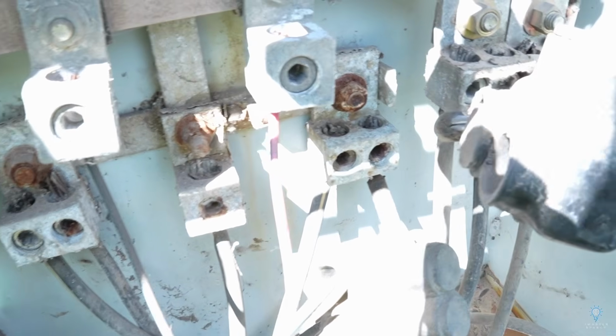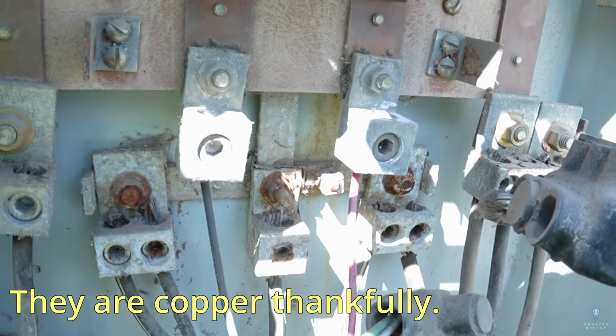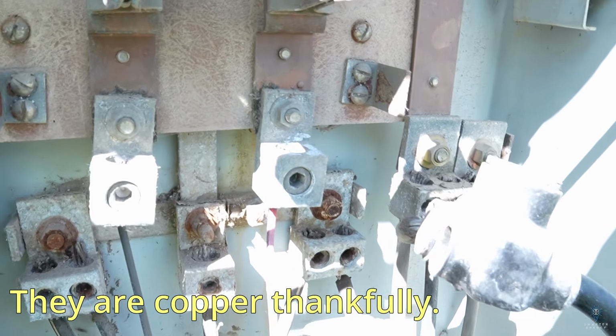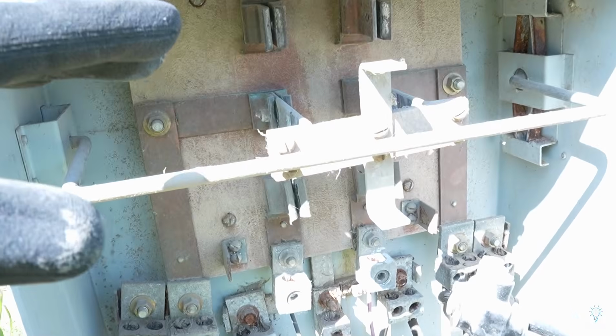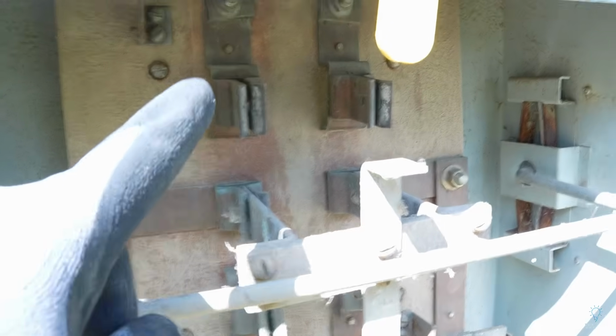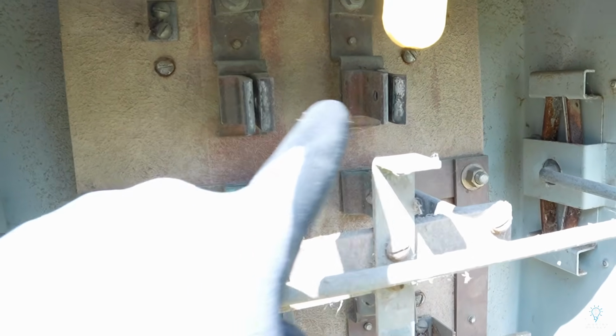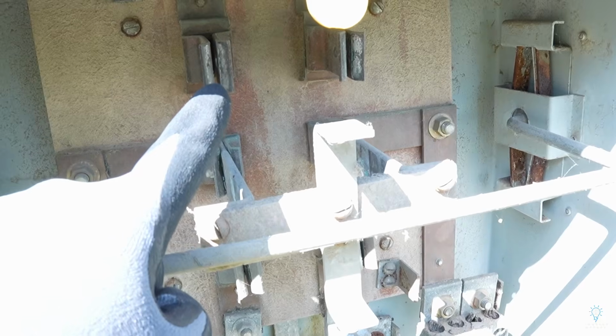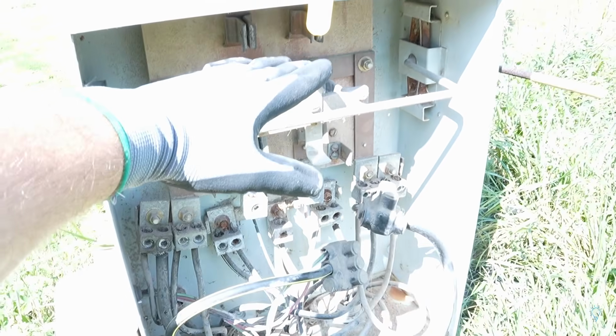So let's try to get that one off. Once we get it off, I'm hoping I'm able to clean up the bus bar. No idea what material that bus bar is. All the other bus bars in here look like copper, but man, those really look like aluminum to me with the way they're corroding. So I guess we'll find out here, but first things first, let's try to get that lug out of there. Again, everything here down is now physically disconnected. Those two lugs right there are still live, but we have physically disconnected the knife switch here, and there is no power from this point down now.